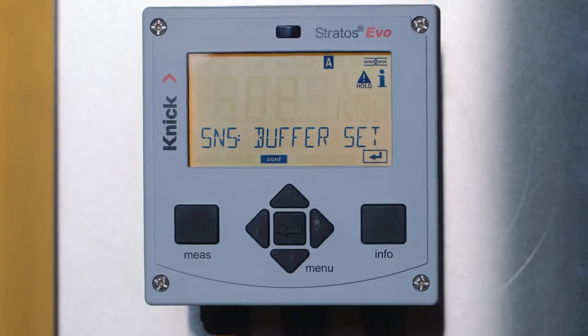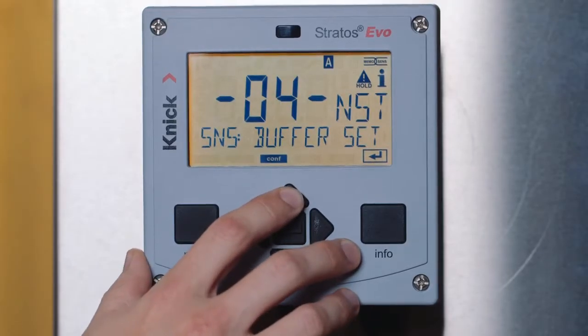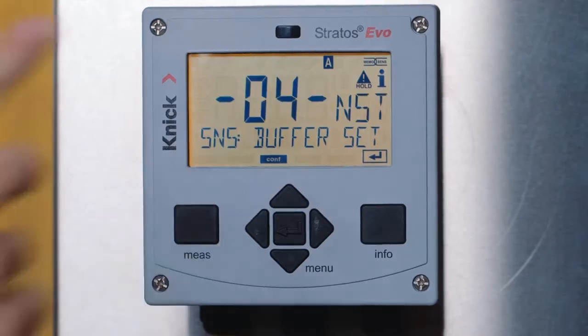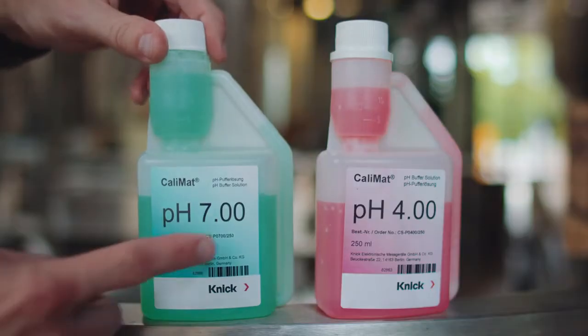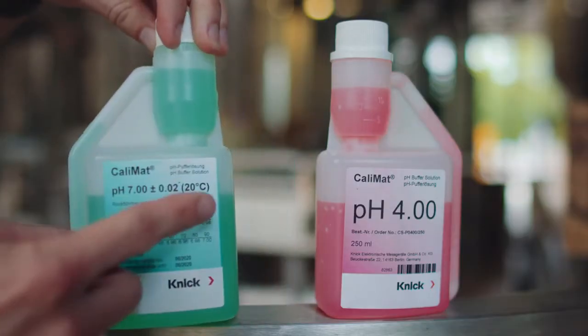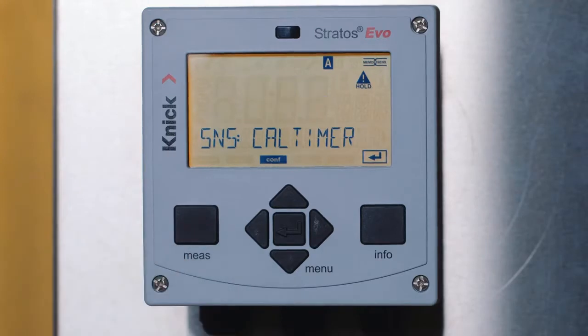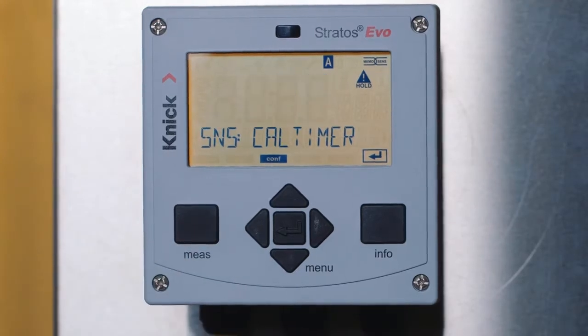You will see that once we select auto under the calibration mode, it offers us the opportunity to select which buffer set we are using. The most common buffer set on the market is NIST Technical, which is option 4 in the transmitter. You can verify your buffer set by checking the labeling on the bottle. The calibration timer allows us to set either a fixed interval or an adaptive evaluation based off sensor loads for indication that a calibration is needed.